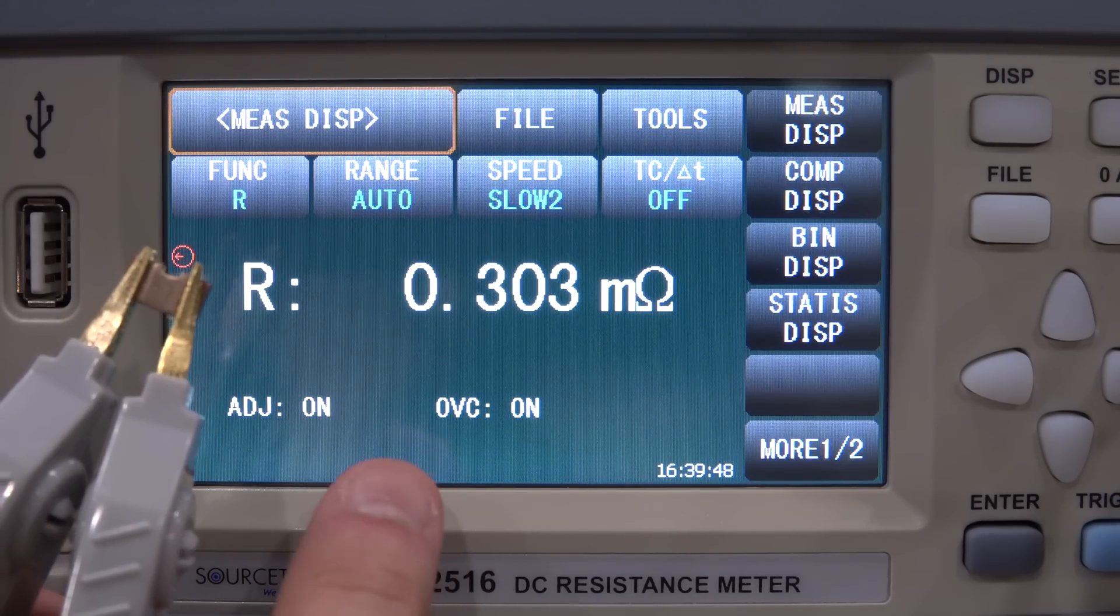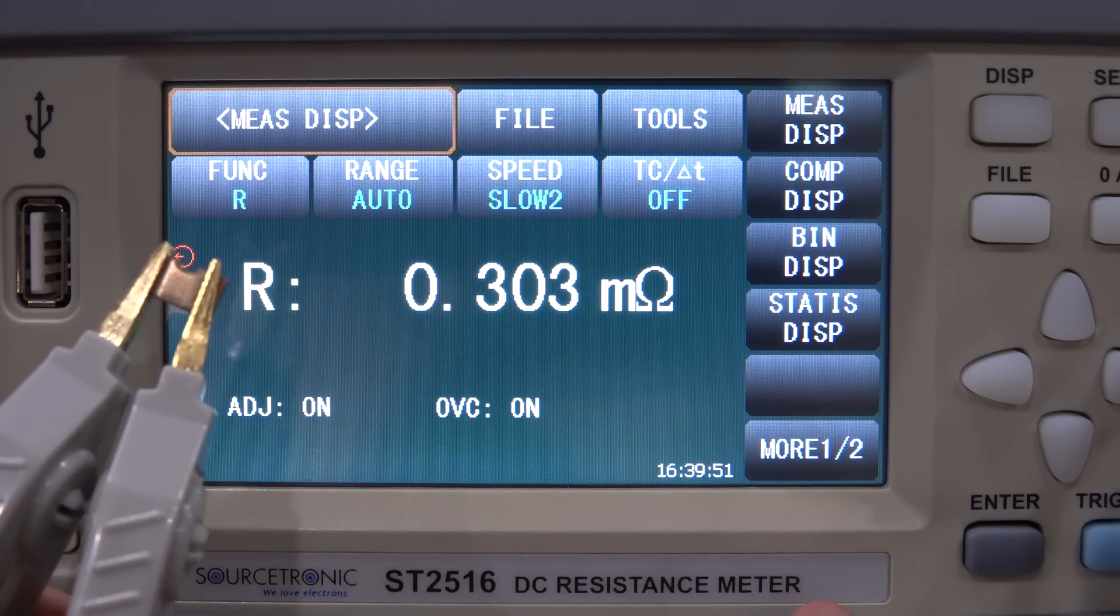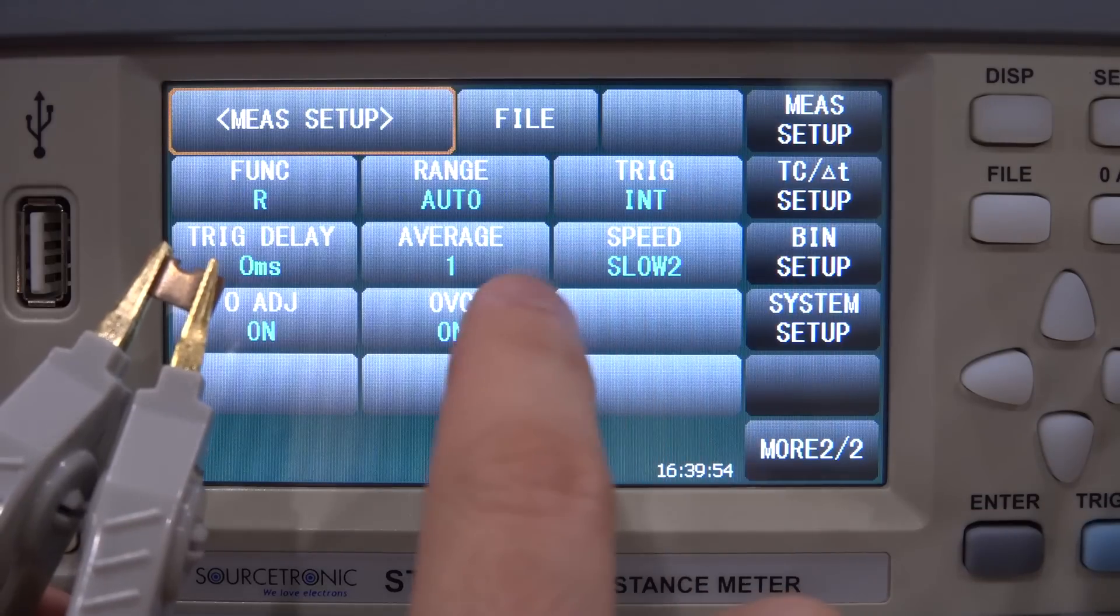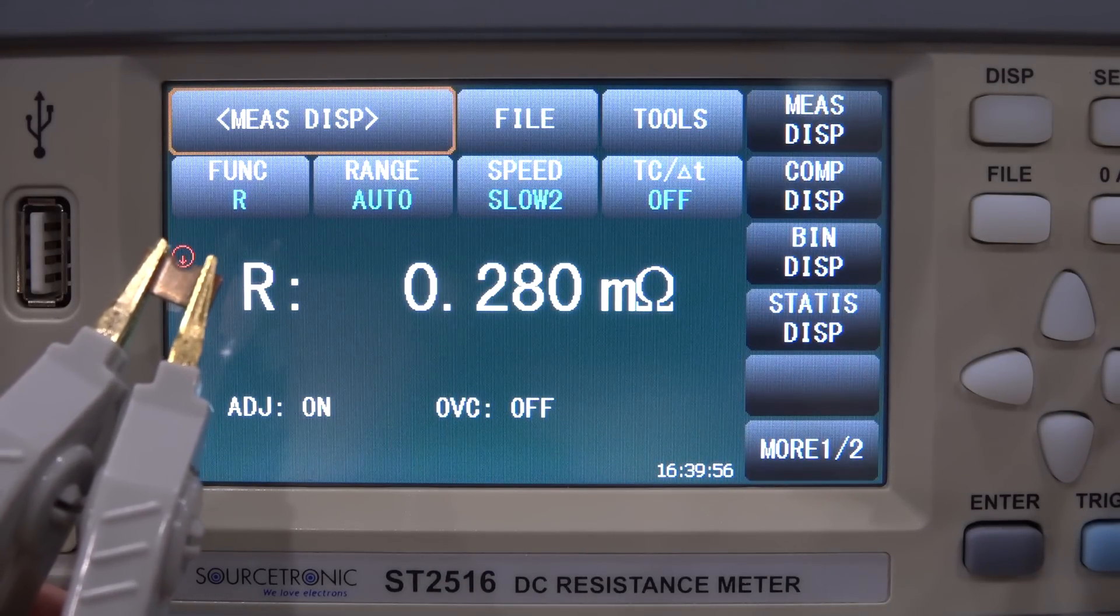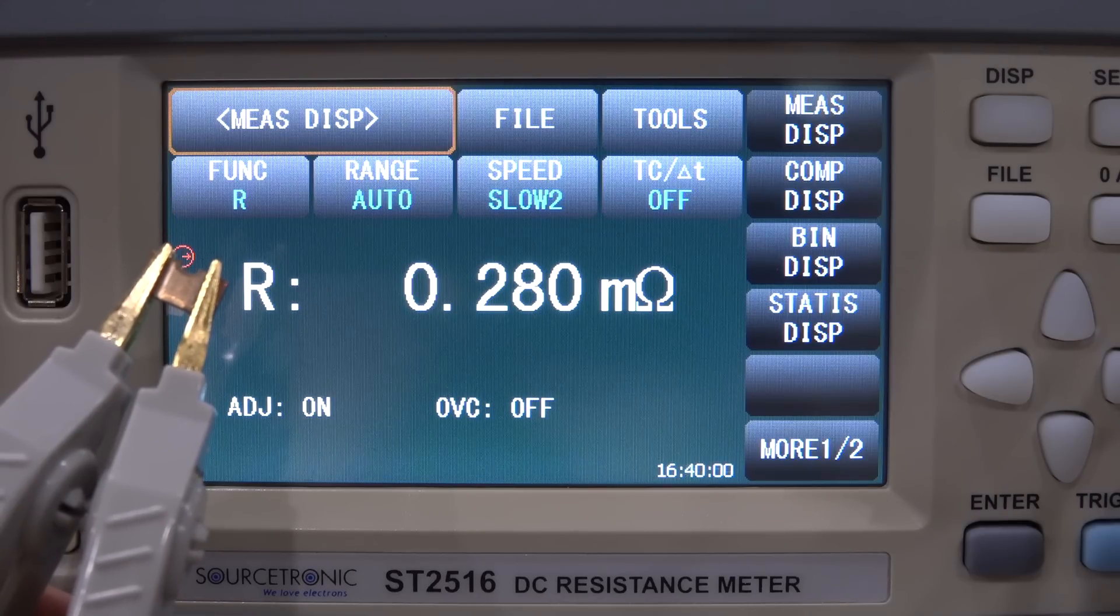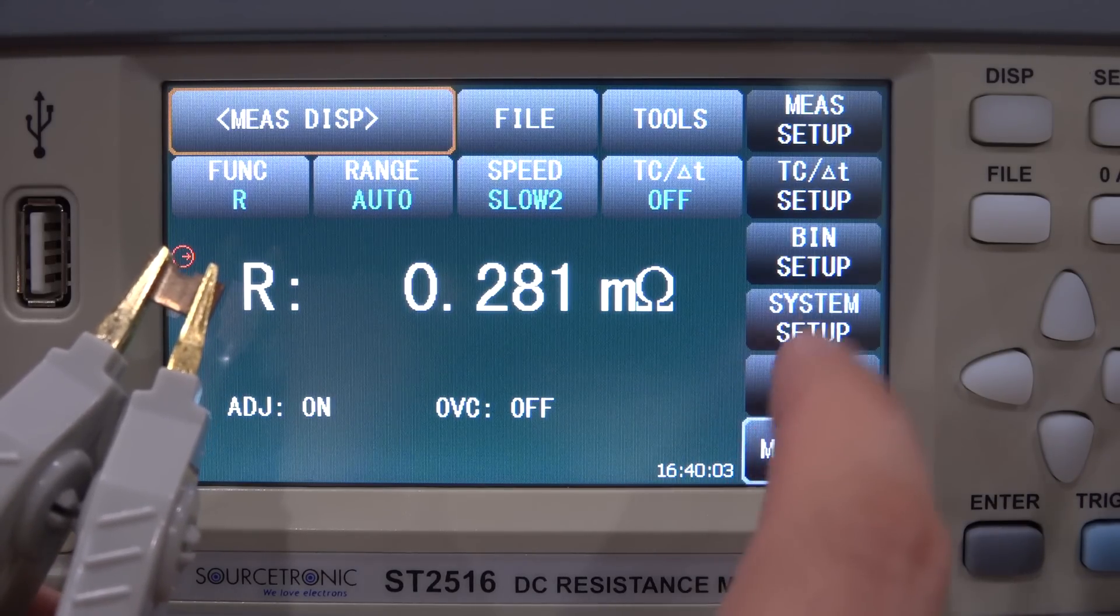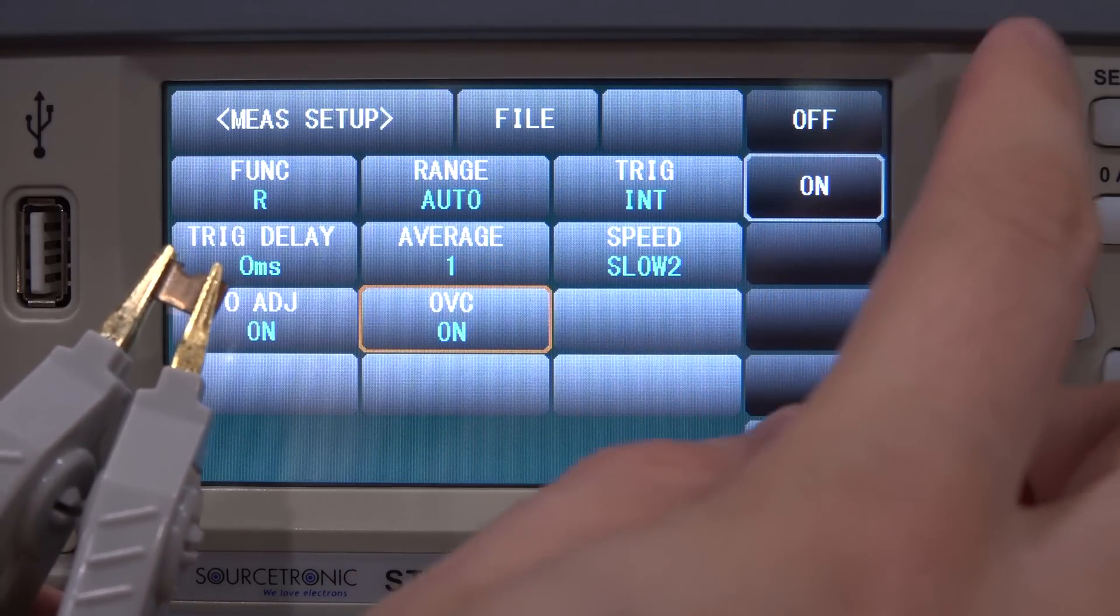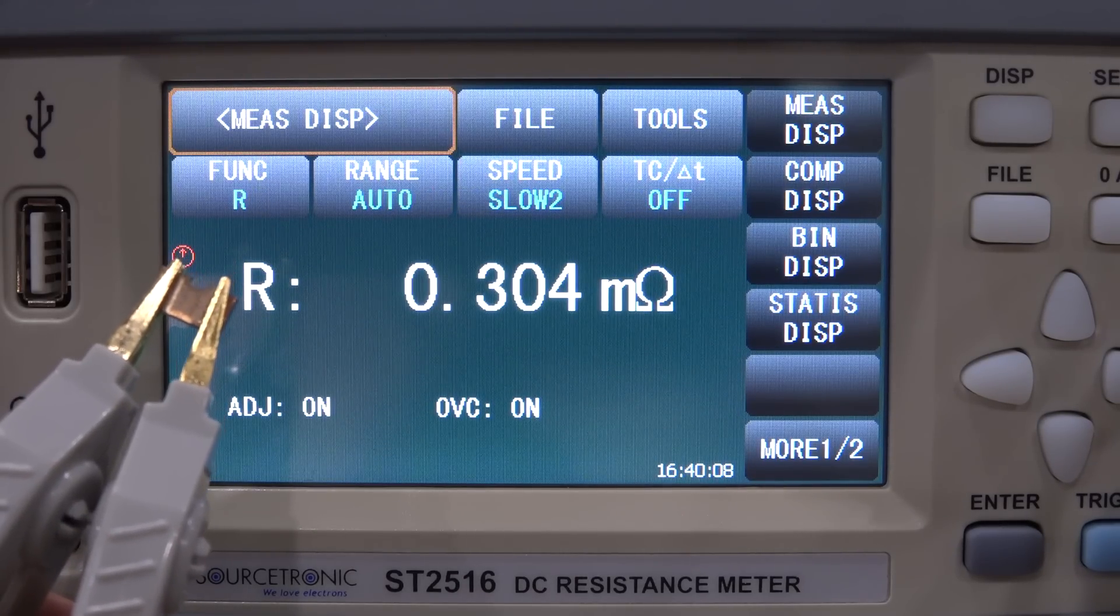And here we are, I think that's a pretty reasonable value, 0.303 milliohm is what it's measuring. Now there is something here called OVC which is offset voltage correction. What happens if we turn that off? Let's go over here, measurement setup and turn this thing off and go back. What are we measuring now? We're measuring 0.280. Now that's not a lot but that's a significant amount when you're looking at a 0.3 milliohm resistor. And go back and enable it again, going back to the original value we had. So what is going on over there?